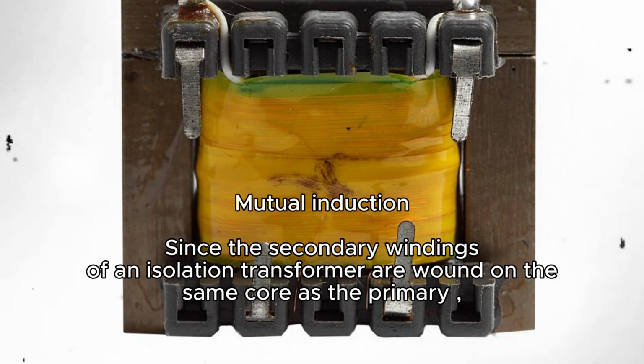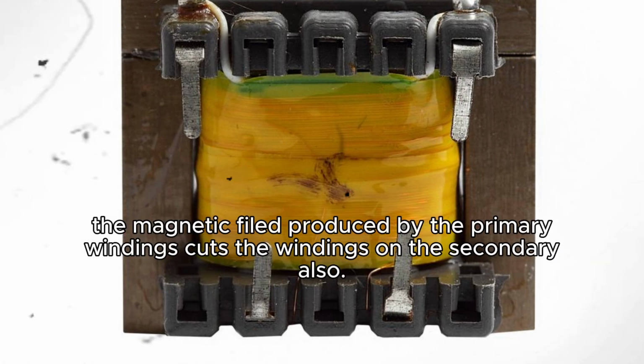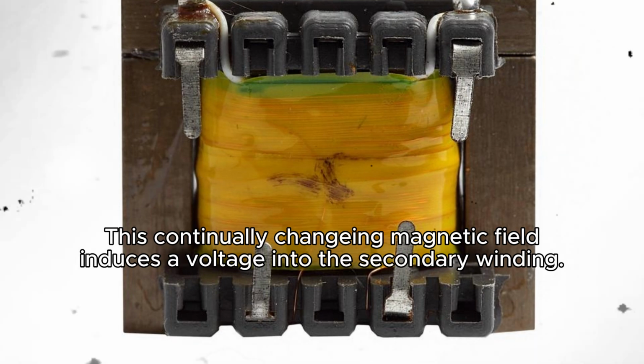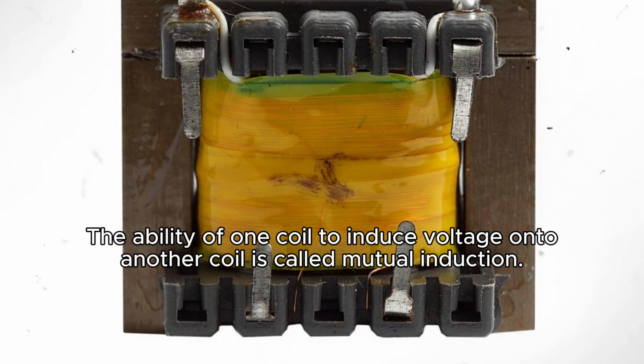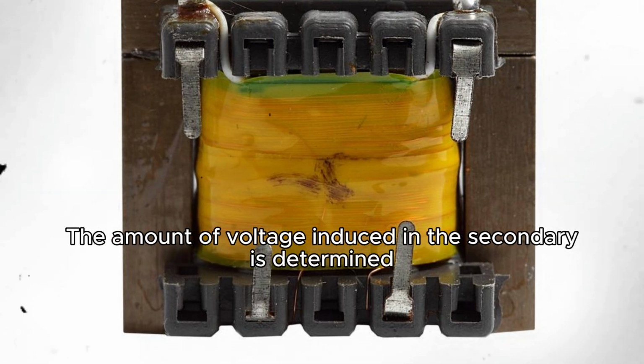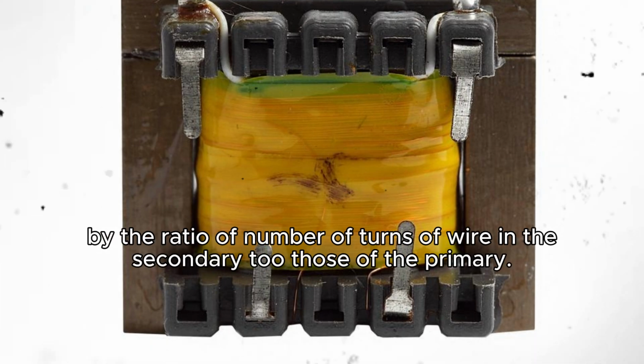Mutual induction. Since the secondary windings of an isolation transformer are wound on the same core as the primary, the magnetic field produced by the primary windings cuts the windings on the secondary also. This continually changing magnetic field induces a voltage into the secondary winding. The ability of one coil to induce voltage onto another coil is called mutual induction. The amount of voltage induced in the secondary is determined by the ratio of the number of turns of wire in the secondary to those of the primary.